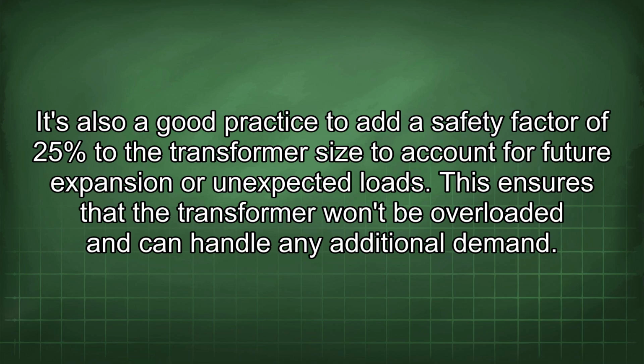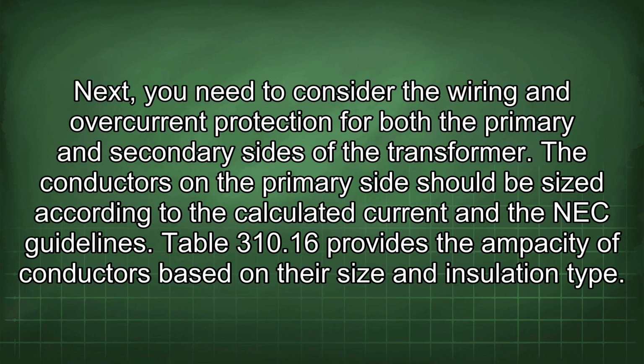It's also good practice to add a safety factor of 25% to the transformer size to account for future expansion or unexpected loads. This ensures that the transformer won't be overloaded and can handle any additional demand. Next, you need to consider the wiring and overcurrent protection for both the primary and secondary sides of the transformer. The conductors on the primary side should be sized according to the calculated current and the NEC guidelines.